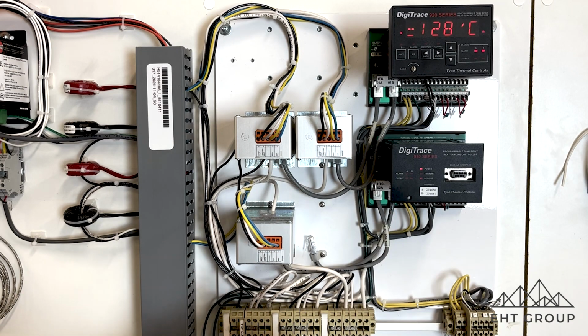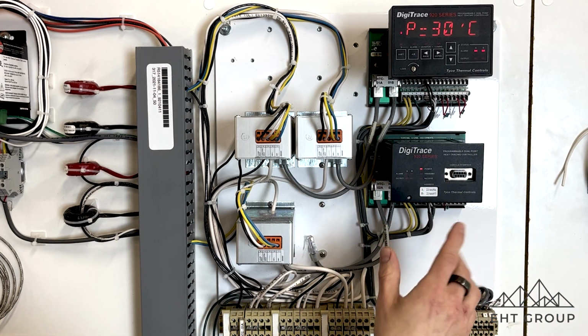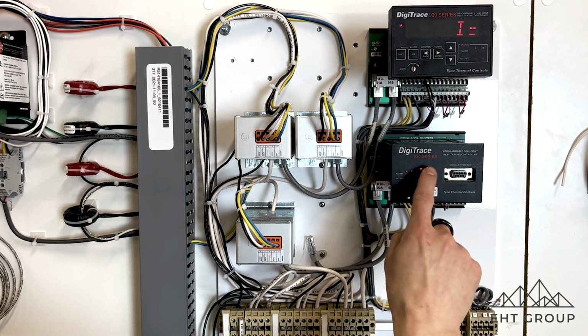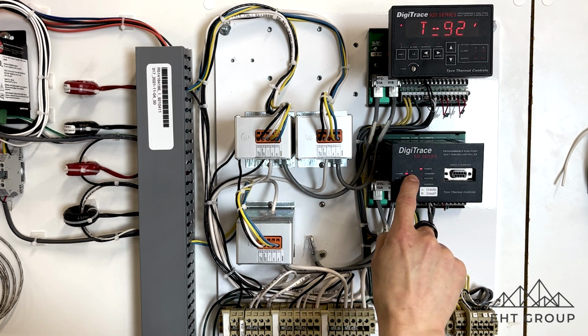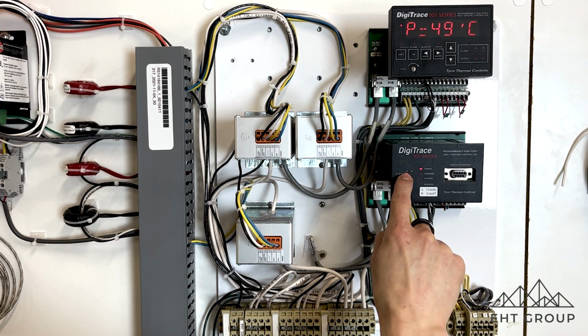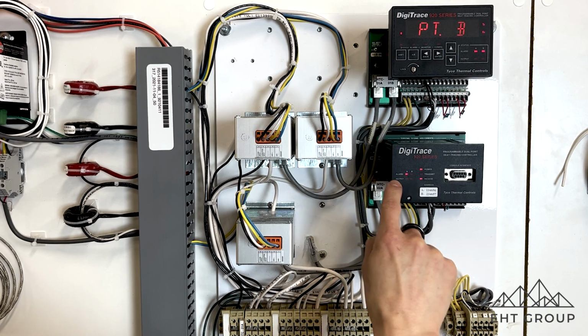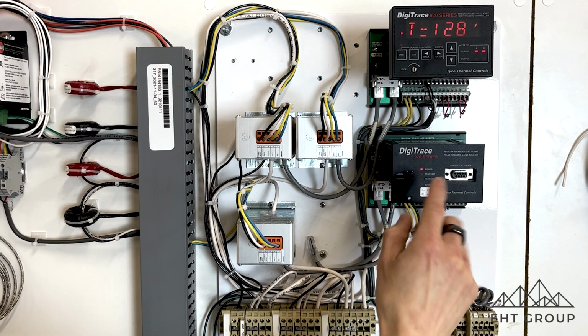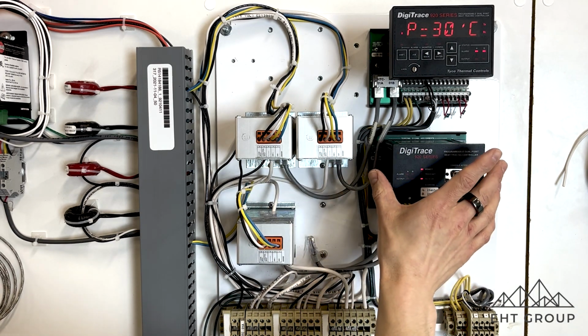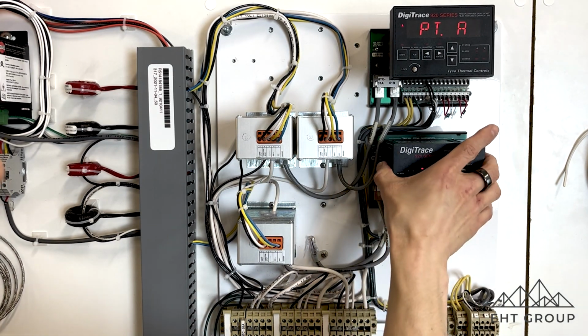So if this is taken off, your heat trace circuit is still going to work and function, and you get some basic indication in terms of power, alarm indication from point A, point B, so circuit 1, circuit 2, and if it's outputting anything to the solid state relays or the EMRs. But this is the actual control module. I've already loosened all the screws on this because I want to show you the control board.